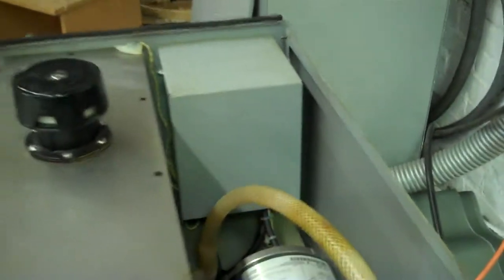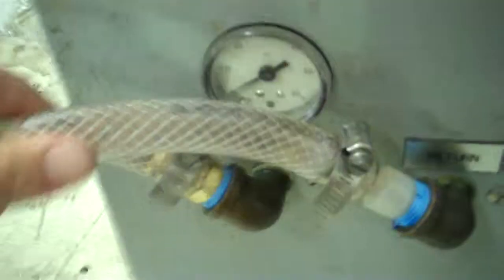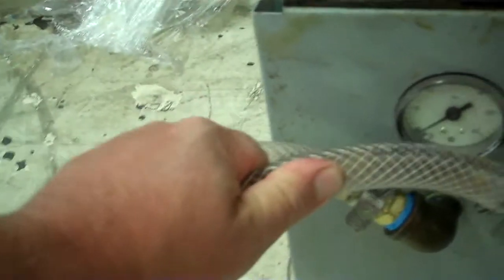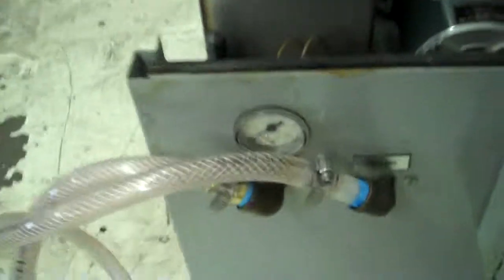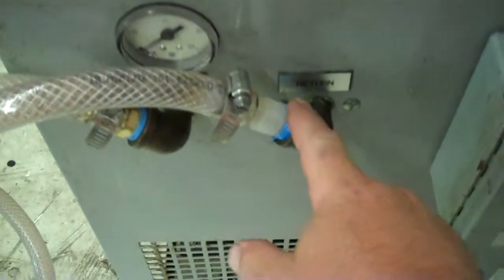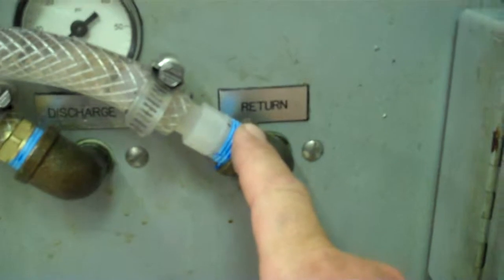Once it hits the set point, one note right now, we're running this is probably about three quarter or half inch lines coming out of the unit. And notice that the water pressure gauge, you should just be slightly above it being zero. If it's pegging up halfway or more, it means your lines are choking the system too much. So if you are running quarter inch lines, you have to have a bypass between the discharge and the return.